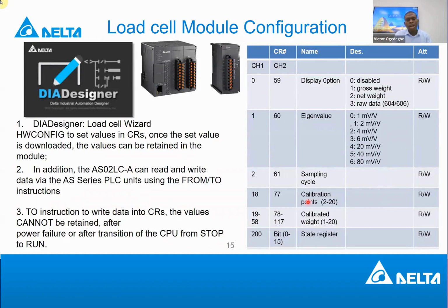So the essence of calibration is to have a very precise digital value that is proportional to the analog signal coming from your load cell or from your load sensor. So you can use this calibration function, look at the registers, write to them, and then you can calibrate the load cell modules. Then it knows that if I read these millivolts from the sensor, this is the digital value that should be available for programming.